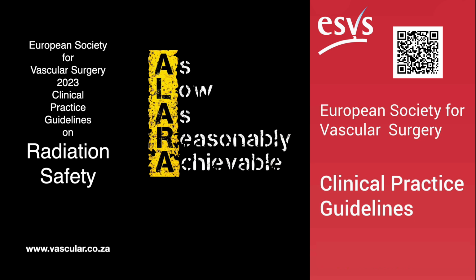That's the idea. Patient positioning is also key for dose reduction. How so? The guidelines strongly recommend positioning the patient as close as possible to the X-ray detector, which is usually part of the C-arm called the image intensifier or flat panel detector. This is a Class 1, Level B recommendation based on physics. Closer to the detector means less dose needed. Significantly less, yes. The closer the patient is to the detector, the less radiation the machine needs to output to get a clear image. It also generally reduces magnification distortion.